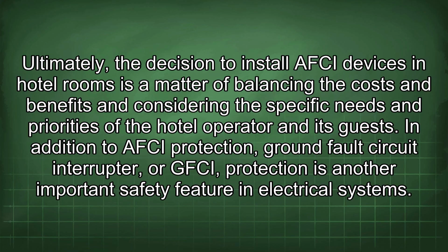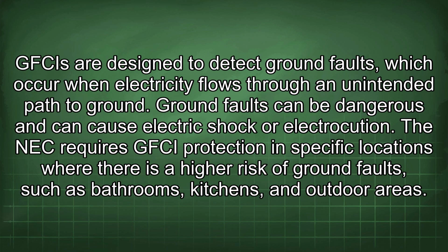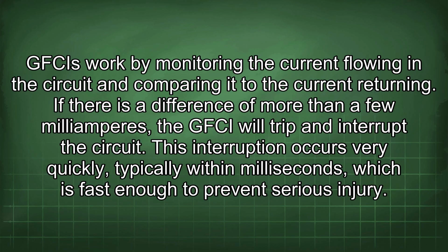In addition to AFCI protection, ground fault circuit interrupter, or GFCI, protection is another important safety feature in electrical systems. GFCIs are designed to detect ground faults, which occur when electricity flows through an unintended path to ground. Ground faults can be dangerous and can cause electric shock or electrocution. The NEC requires GFCI protection in specific locations where there is a higher risk of ground faults, such as bathrooms, kitchens, and outdoor areas. GFCIs work by monitoring the current flowing in the circuit and comparing it to the current returning. If there is a difference of more than a few milliamperes, the GFCI will trip and interrupt the circuit.